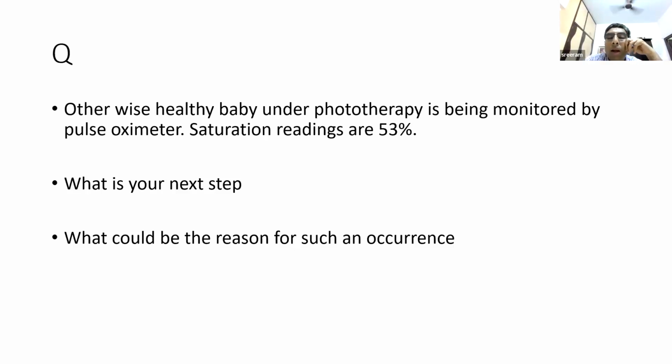It is an intense light, isn't it? Phototherapy is working by light. So when you have an additional light, it interferes with the signal. So the sensor gets confused because of excessive ambient light. That is why it is always a good idea to cover the probe when a baby is under phototherapy. Good. I think there is one more last one.